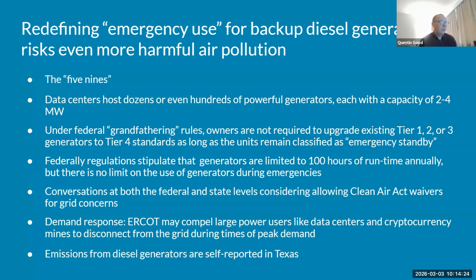When there's stress on the grid, that level of uptime might not be possible without backup generators. So all data centers keep some amount of backup power, and the preferred source is diesel generators. Usually data centers will have dozens of these, enough to power a mid-sized city. Current regulations limit data centers to 100 hours of diesel generator runtime annually.